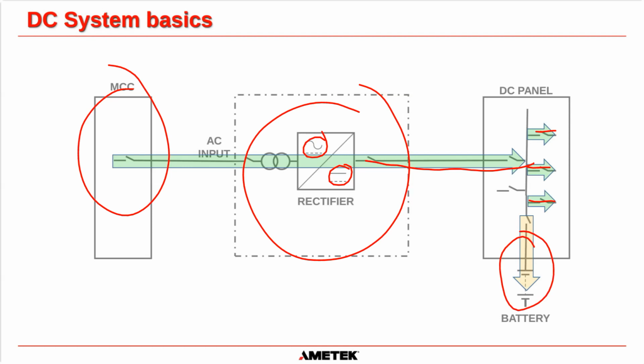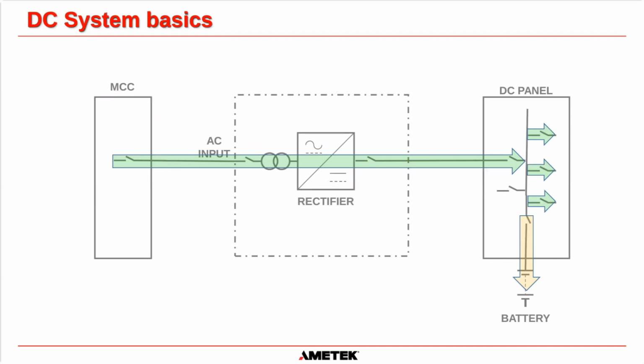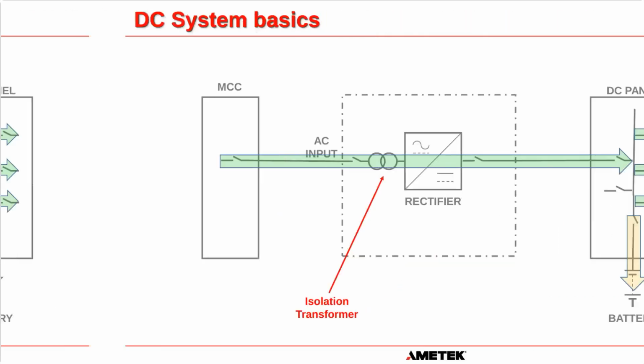This is just a really good design of system because you can separate the battery from the system. You can separate the charger from the system. And in truth, you could add an additional charger in here if you needed to replace this charger and use it as a temporary. So it's very flexible, this DC system. I do like this design. Okay, so that's the very basics of a DC system. And your loads are going to be basically switchgear systems. It could be DC lube oil pumps if it's a station battery in a power station. There's a whole load of DC loads that can be supplied.